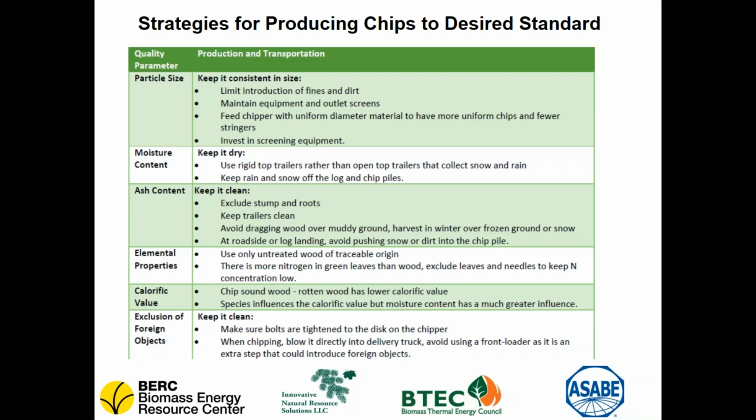Again, this is a difference between this market and the large industrial market. You don't produce clean chips if you pile them on unpaved pads. Often the gravel and dirt that you add during loading into your truck for delivery aren't accounted for in the standards testing that you've done to certify your fuel as meeting a particular ash content. But when the customer receives it, if they do their own test and it contains lots of parking lot gravel or soil or bark from whatever's on the deck, that can compromise the quality and compromise the functional performance. So next slide.